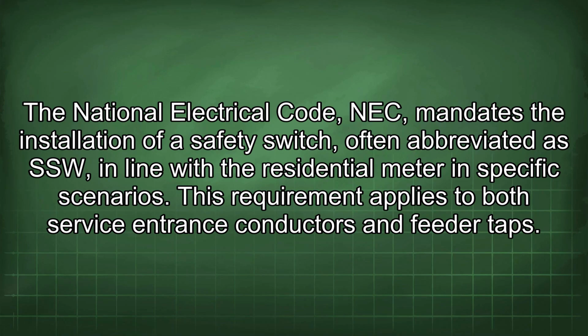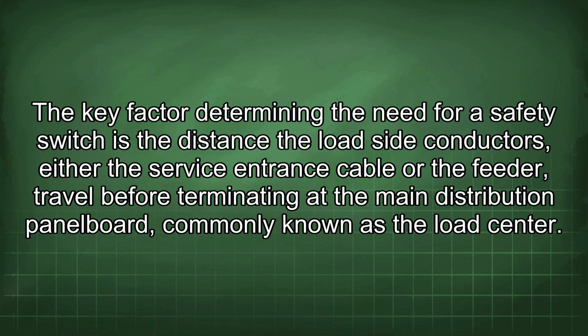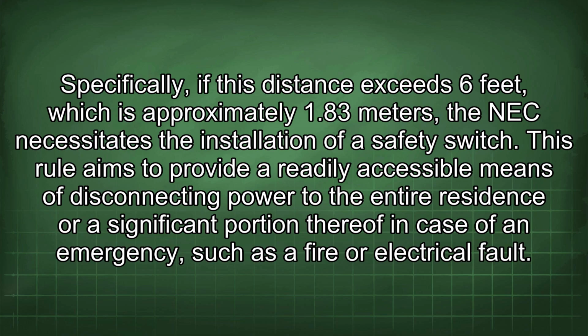National Electrical Code (NEC) mandates the installation of a safety switch, often abbreviated as SSW, in line with the residential meter in specific scenarios. This requirement applies to both service entrance conductors and feeder taps. The key factor determining the need for a safety switch is the distance the load side conductors, either the service entrance cable or the feeder, travel before terminating at the main distribution panel board, commonly known as the load center.